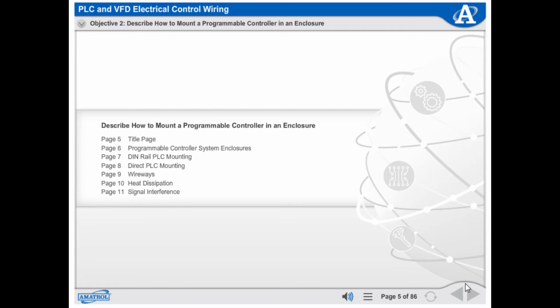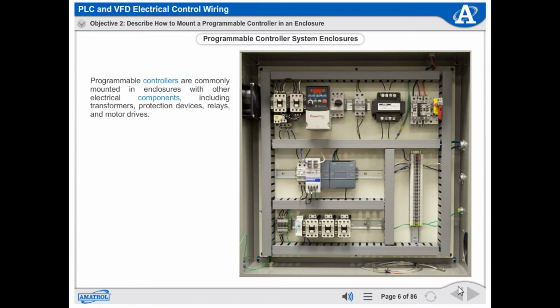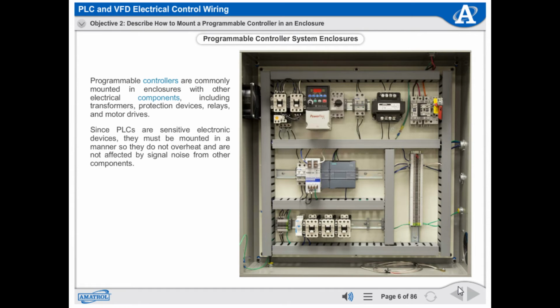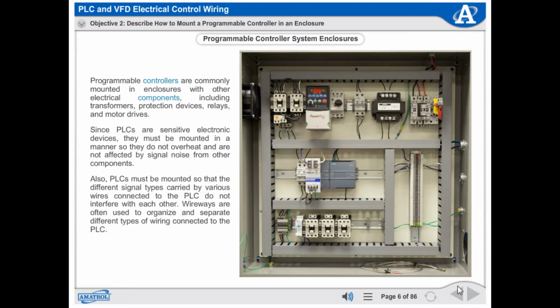Describe how to mount a programmable controller in an enclosure. Programmable controllers are commonly mounted in enclosures with other electrical components, including transformers, protection devices, relays, and motor drives. Since PLCs are sensitive electronic devices, they must be mounted in a manner so that they do not overheat and are not affected by signal noise from other components. Also, PLCs must be mounted so that the different signal types carried by various wires connected to the PLC do not interfere with each other. Wireways are often used to organize and separate different types of wiring connected to the PLC.